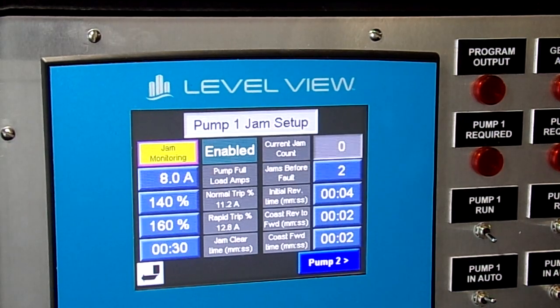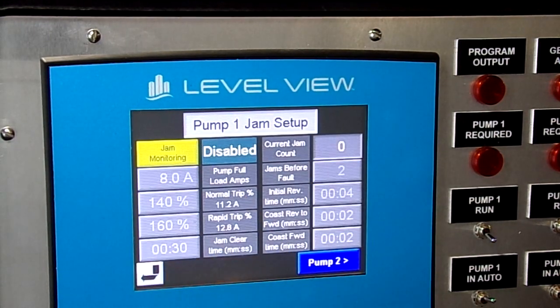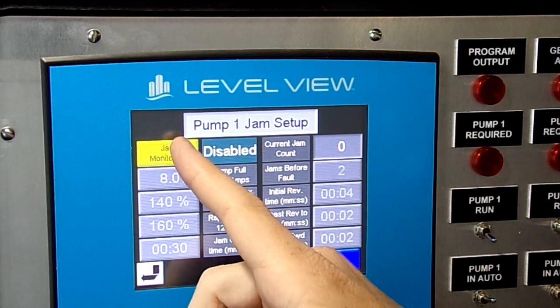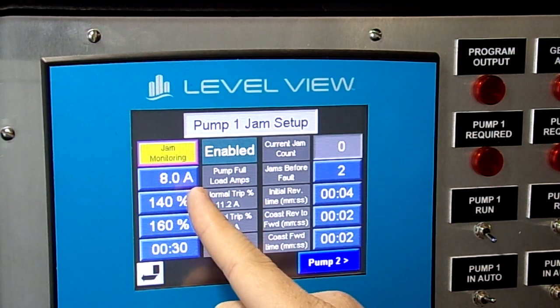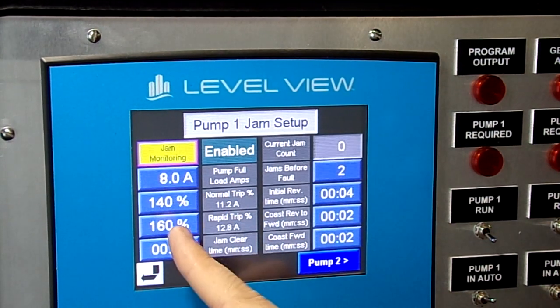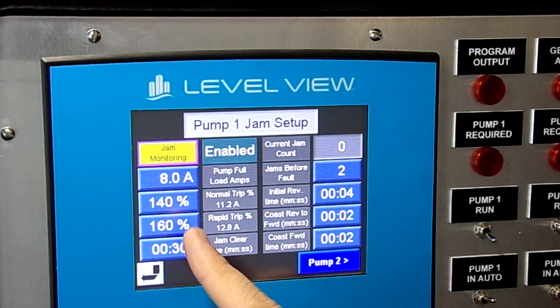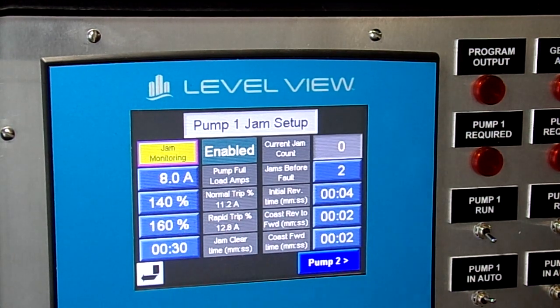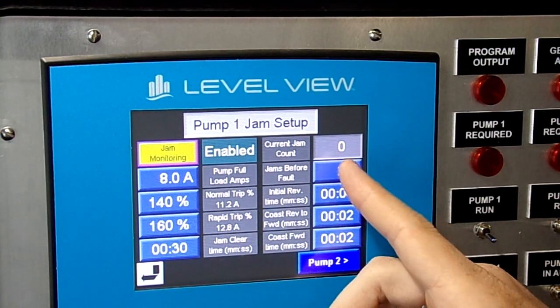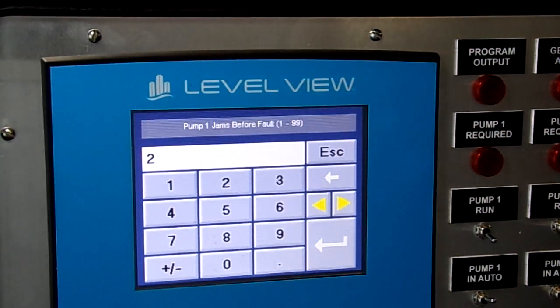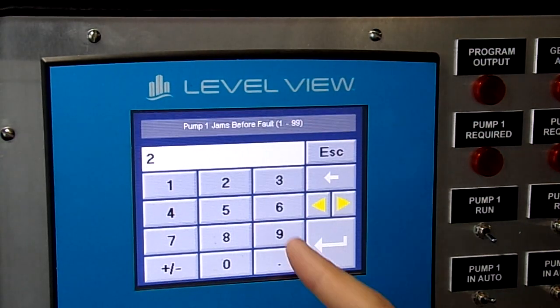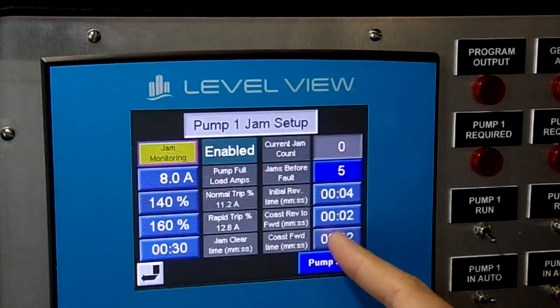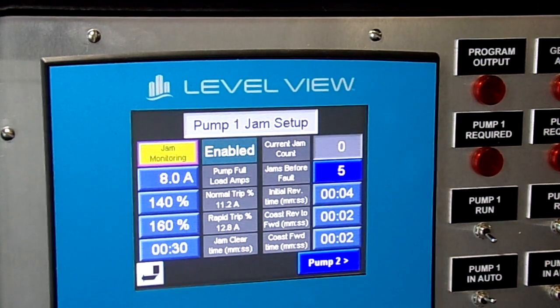So our jam detection setup will come as disabled from the factory and will need to be enabled. We will need to insert our pump full load amps here, and then we also have our percent trip over, and we also have a rapid trip over. We also have a timer for how long it takes the jam to clear. We can change how many jam cycles that this station comes through, from 2 to 5, or from 1 to 99.